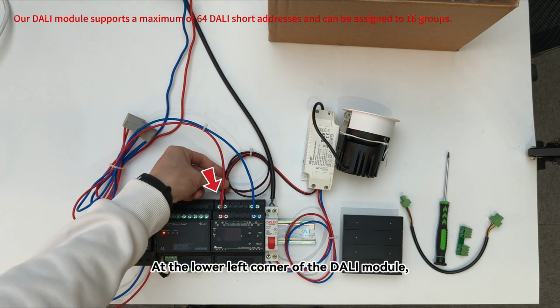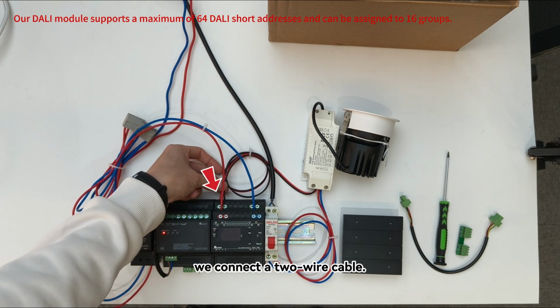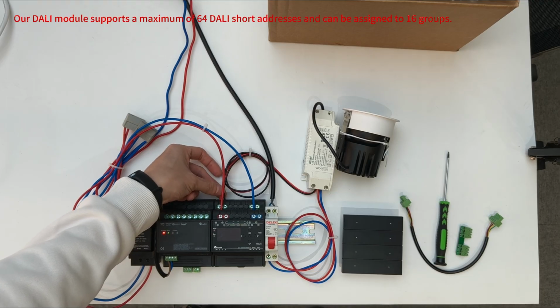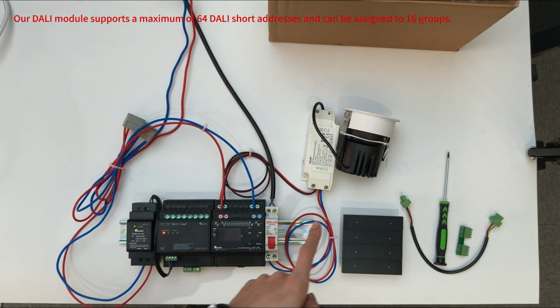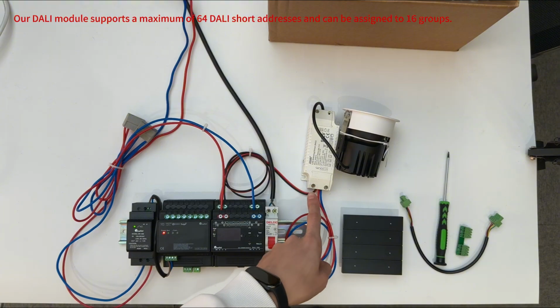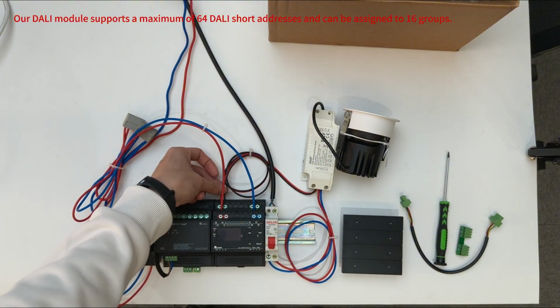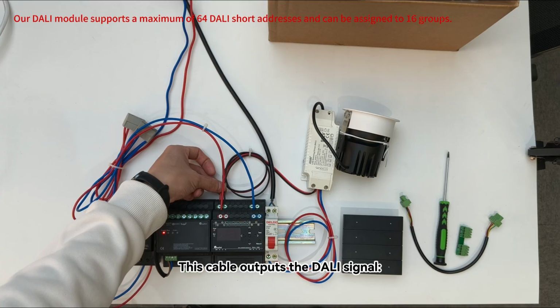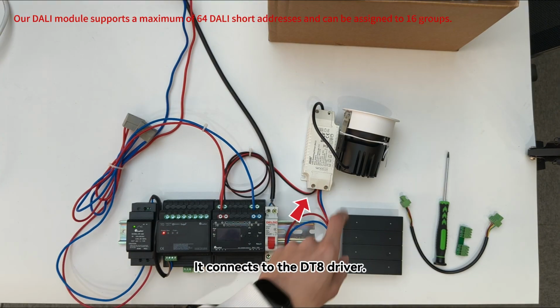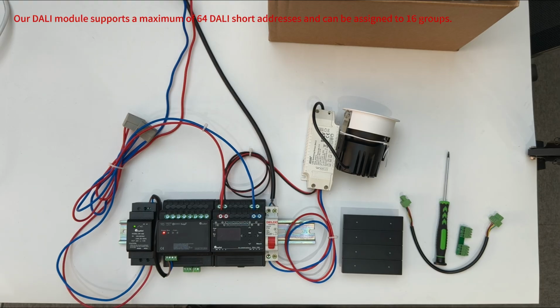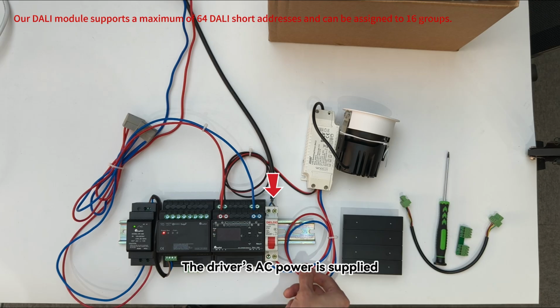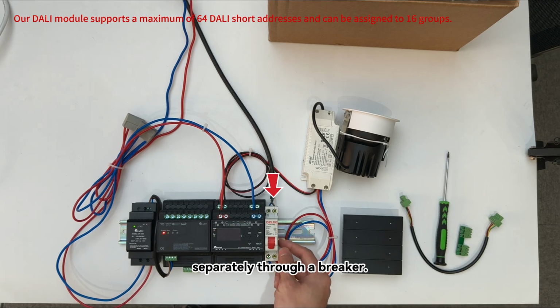At the lower left corner of the DALI module, we connect a 2-wire cable. This cable outputs the DALI signal, positive and negative. It connects to the DTA driver. The driver's AC power is supplied separately through a breaker.